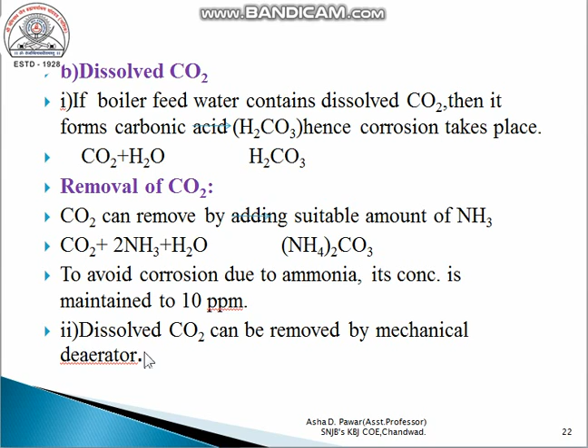And to avoid corrosion due to the ammonia, since basic condition again causes corrosion, its concentration is maintained at 10 ppm only. Above that we don't use ammonia, because then basic condition occurs and corrosion may take place. One more method used to remove the dissolved CO2 is the mechanical deaerator, that is, boiling the water at a proper temperature and pressure to remove the dissolved O2 and CO2.